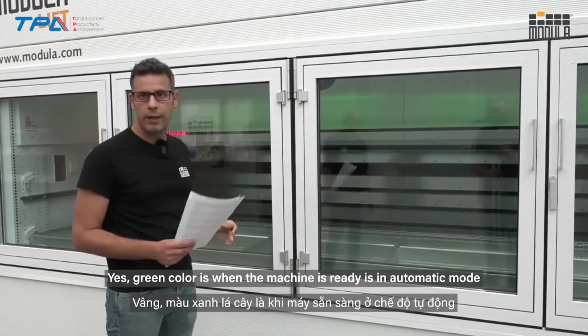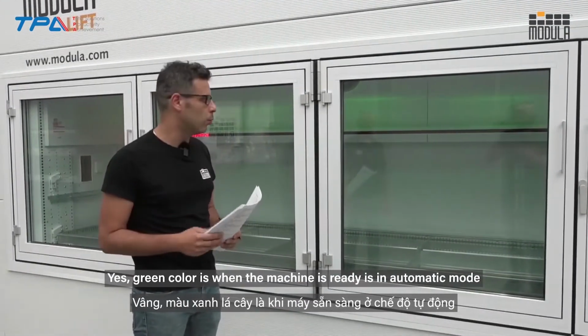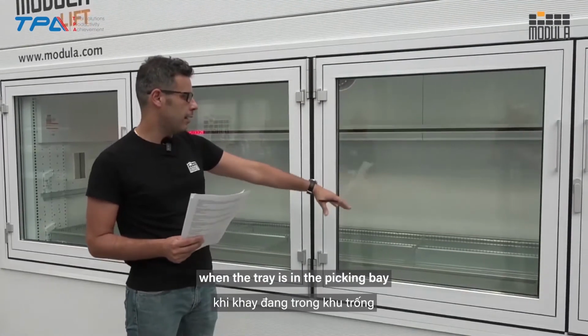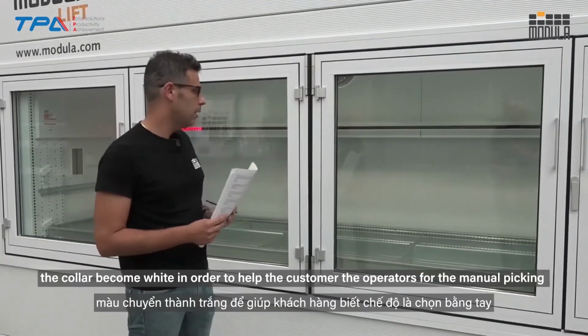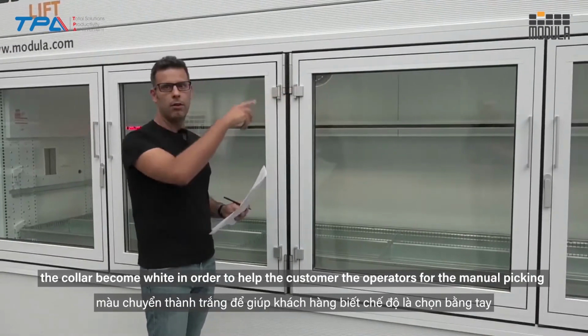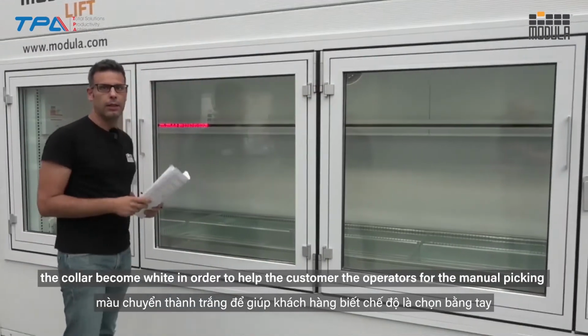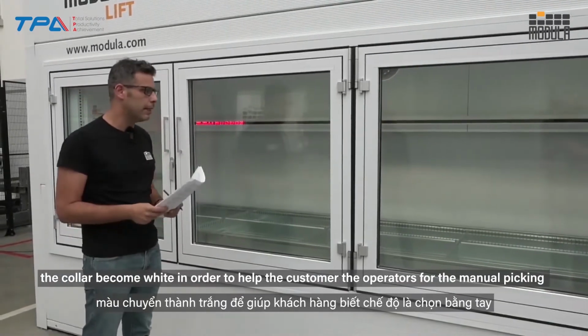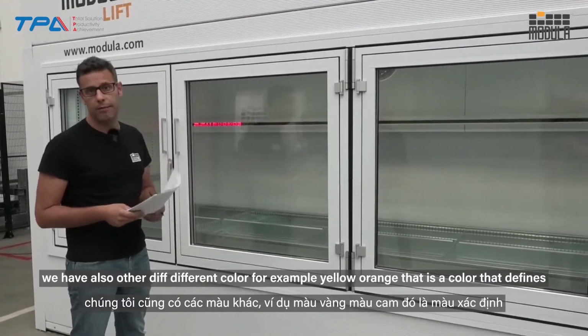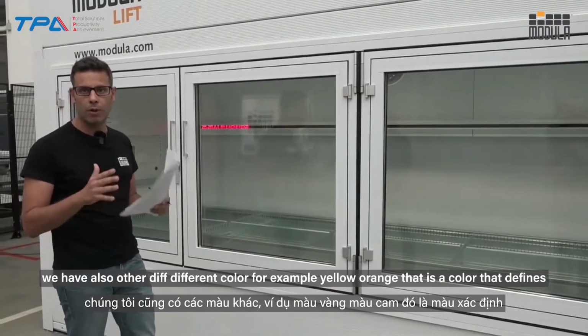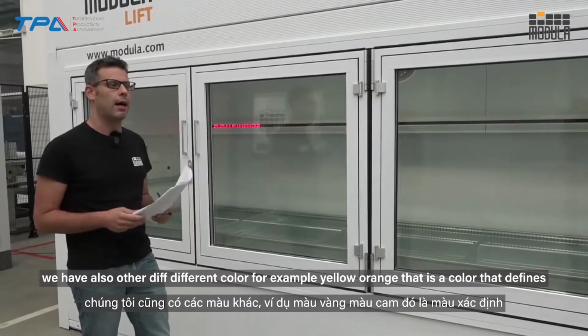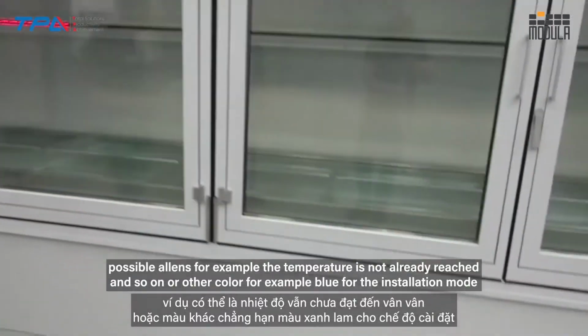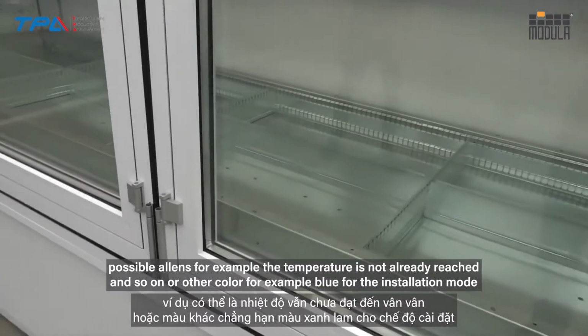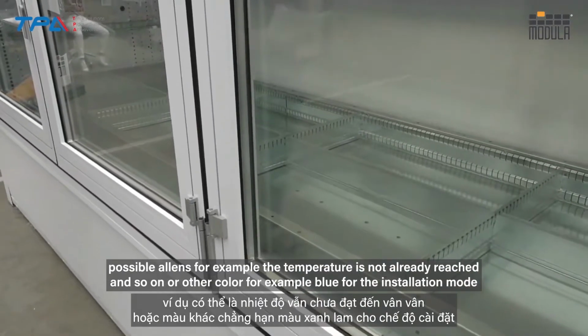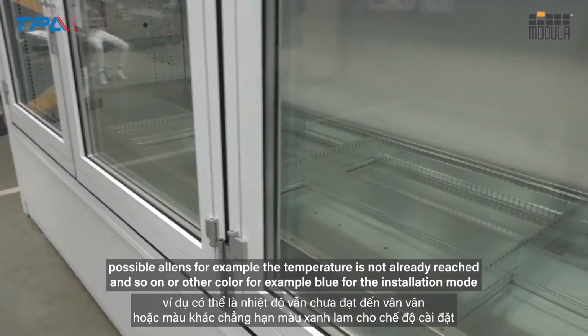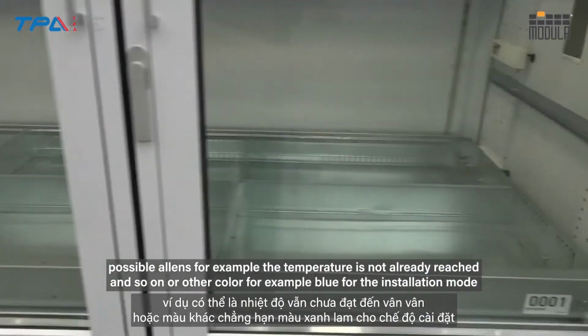Yes, the green color is when the machine is ready, in automatic mode. When the tray is in the picking bay, the color becomes white in order to help the operators with manual picking. We also have other colors, for example yellow or orange, that define possible alarms, for example when the temperature is not yet reached, and so on, or other colors, for example blue for the installation mode.